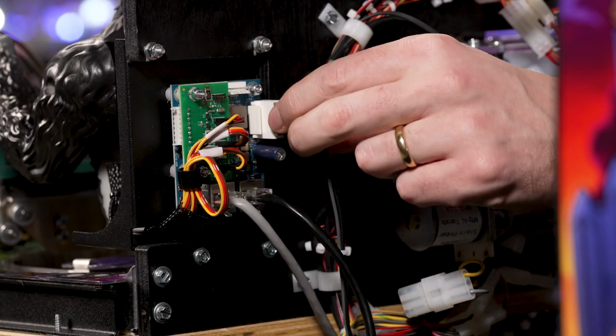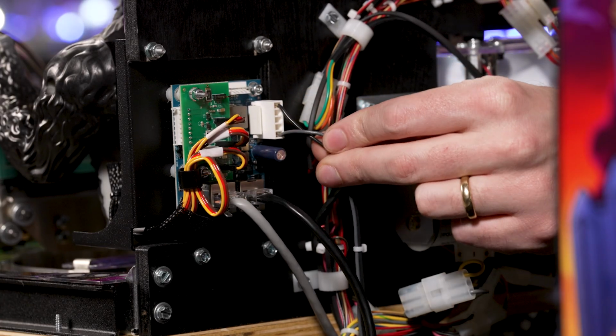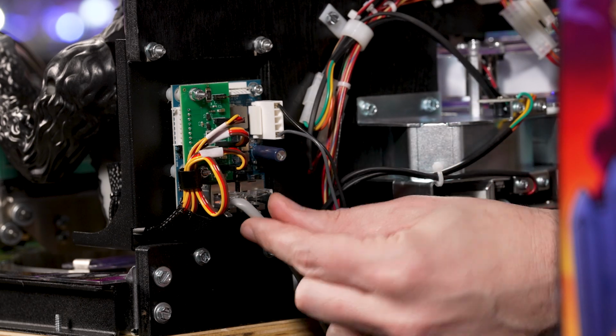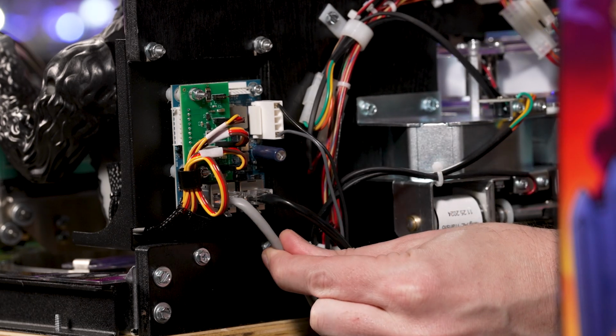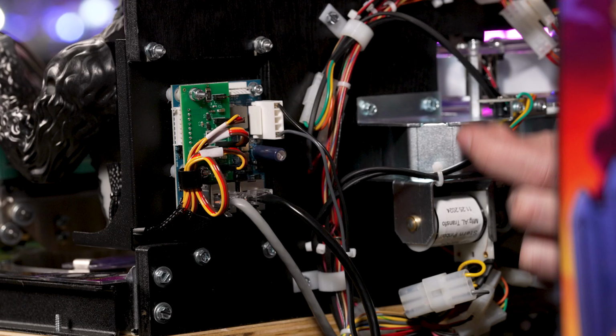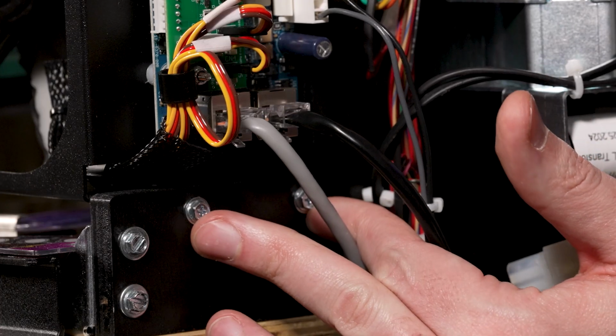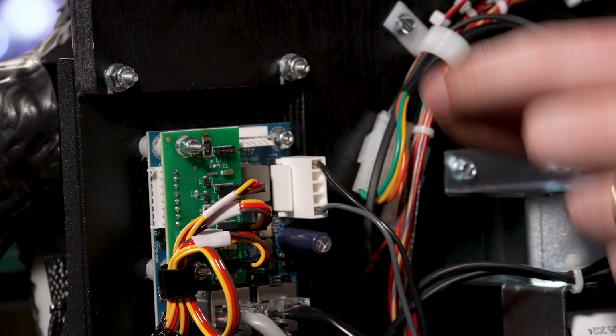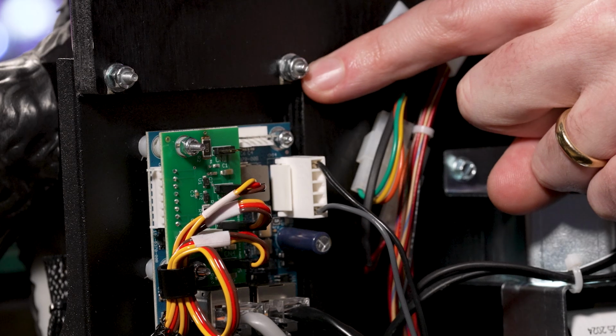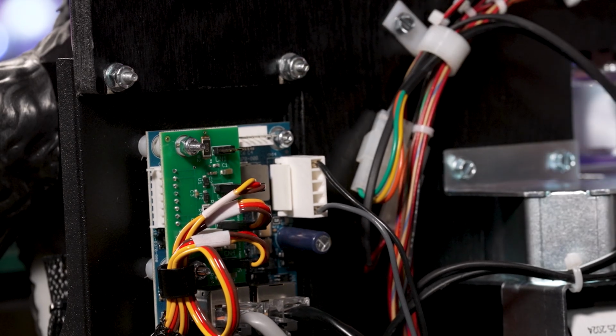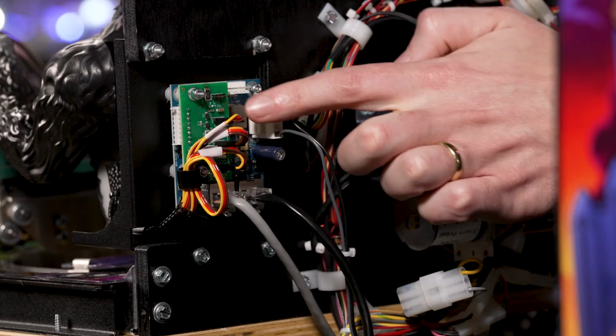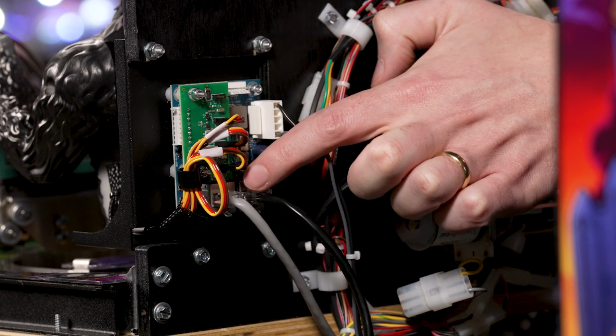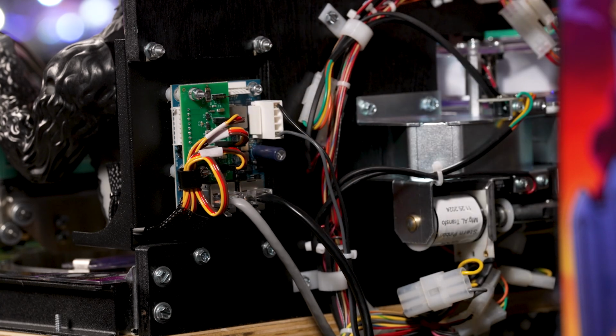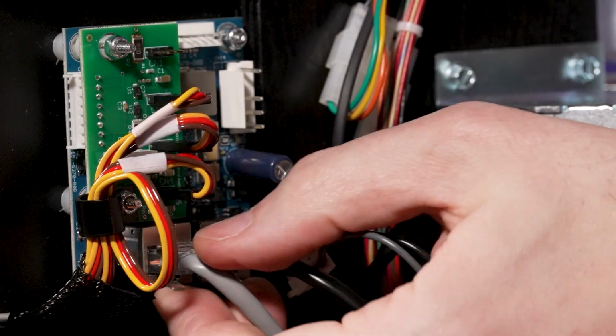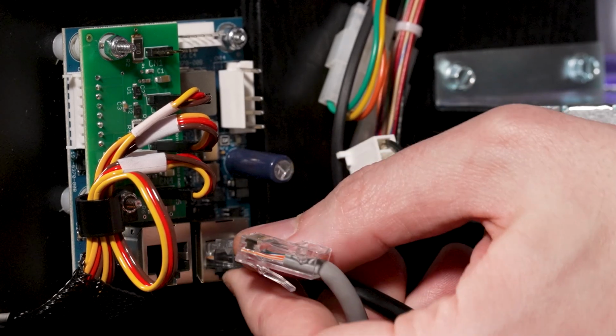So we have our 48-volt power to the node board here, and we've got our 2 data lines for the data bus here. We will need to remove the 2 1/4 inch head screws here and the 2 5/16 inch nuts that hold the assembly into the back panel. These connections on the board do not need to be moved, so do not touch those. Just the 2 data and 48-volt power connections.